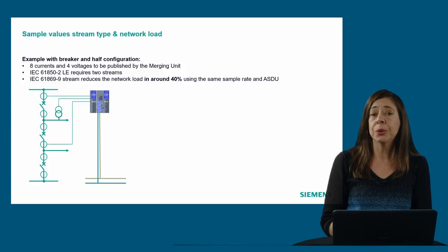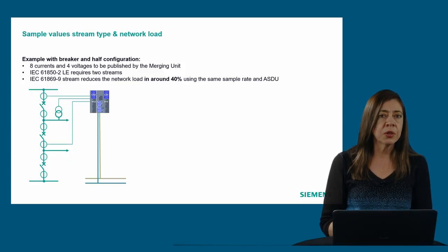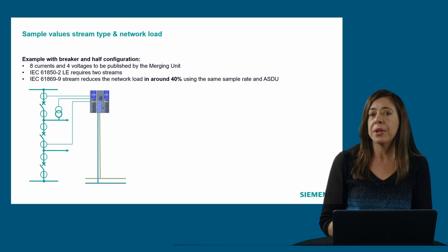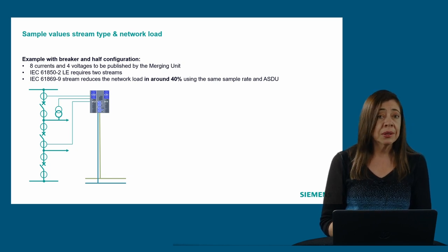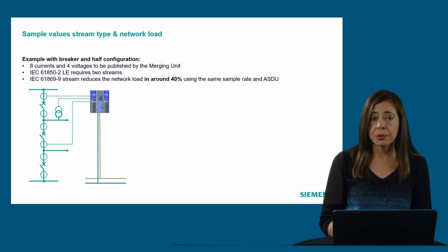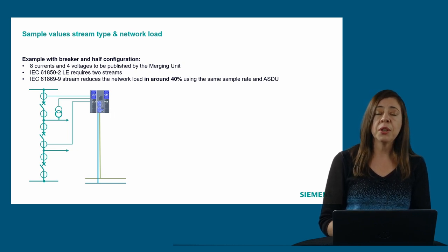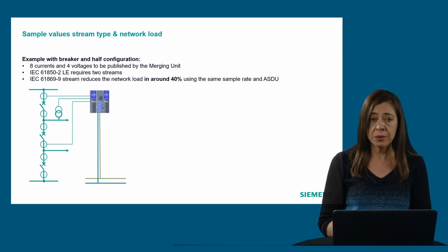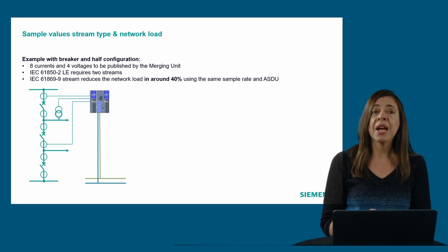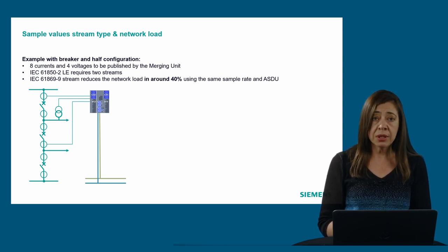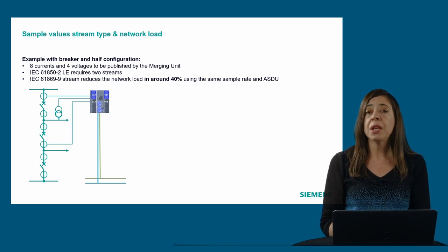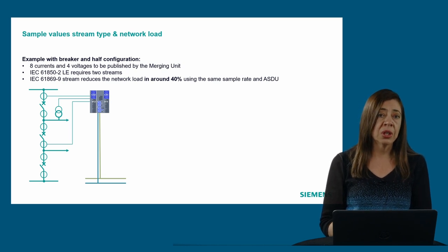So let's start talking about the influence of the type of the stream in our network. And we can do it with an example. So here we have one substation in a circuit breaker and a half configuration, and we take the upper diameter where we need to transmit 8 different currents and 4 voltages.